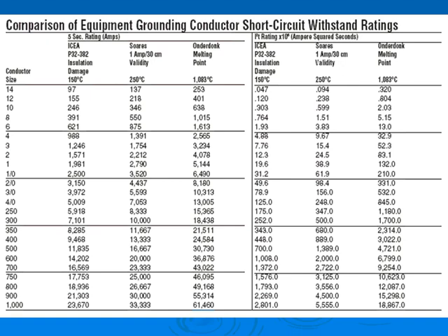So you have a number 14 can withstand this amount of current for 5 seconds. Remember, it's 5 seconds. If it's rated 150 degree, 250, and all these temperatures. So we'll give you guys the ampacity, basically related to the damage curve for the conductor based on multiple standards.